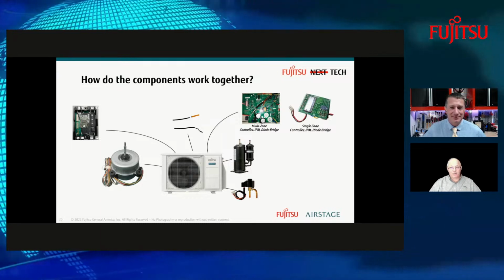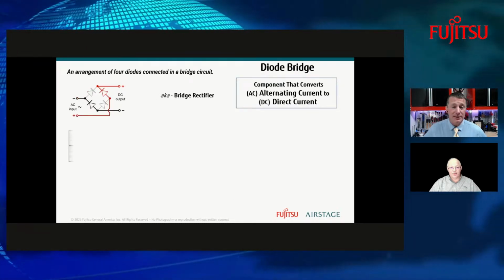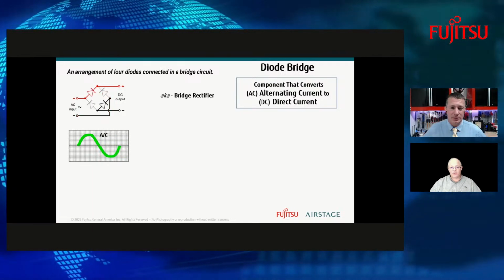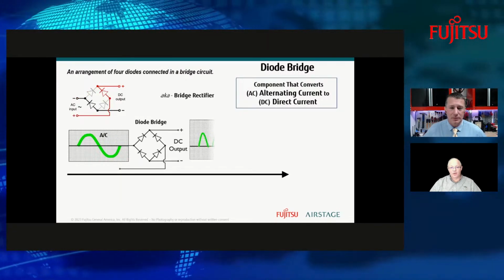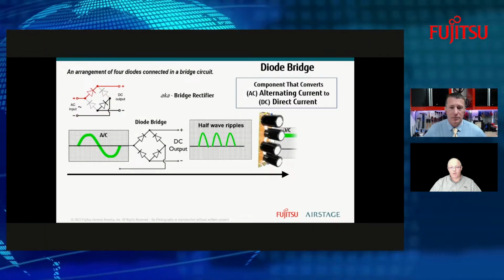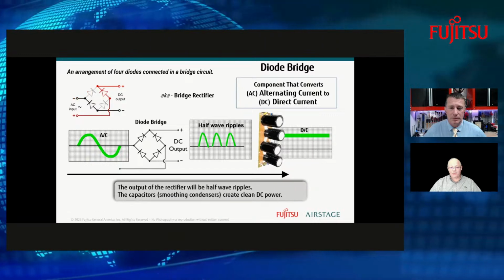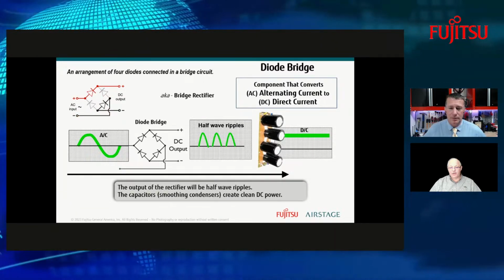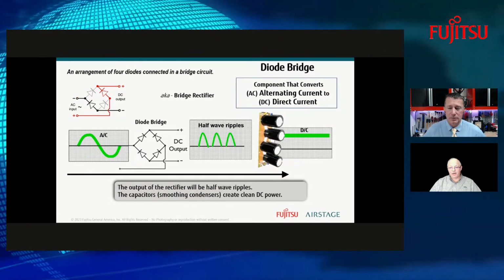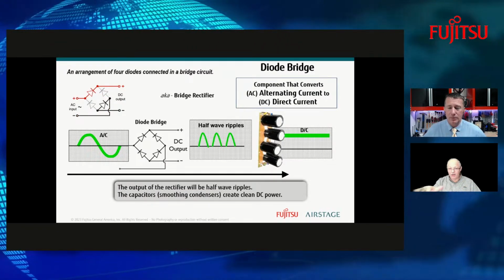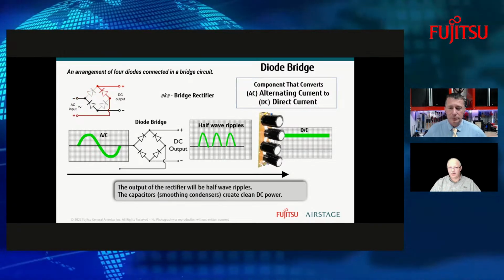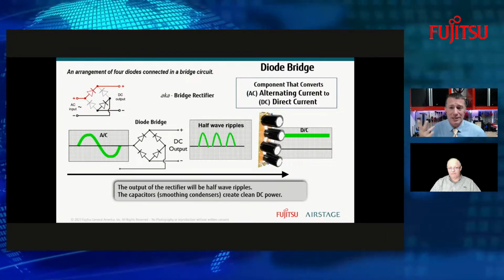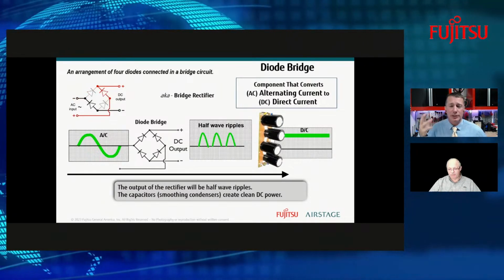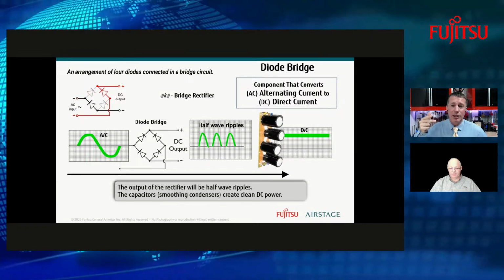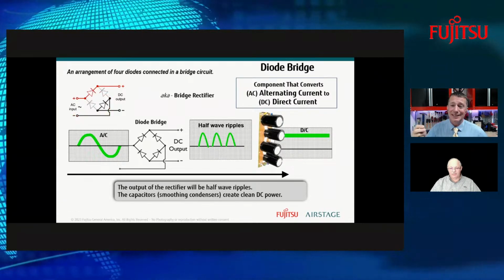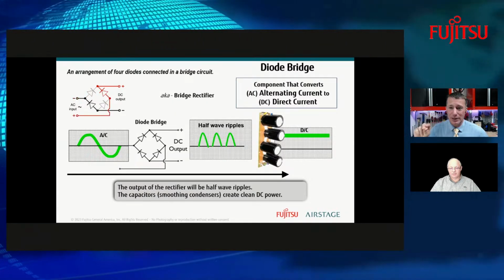Right. So let's talk about how the components work together. Yeah, definitely. A lot of guys have probably seen some things like this before, but we have the AC coming in. We go through the diode bridge, and you have what we call half-wave ripples, and then we go through a bank of capacitors, and we're trying to clean up that DC power. And so that's just the basics of how we make it through there to get that final good clean DC. So we come in as typically, if we're talking a residential application, whether it's 120 or 208, 230, 240 volt, we have single phase AC coming in, going through our bridge rectification circuit, turning it into a DC supply voltage right at our capacitor banks.